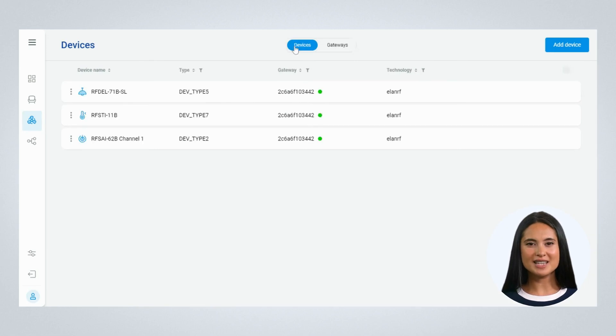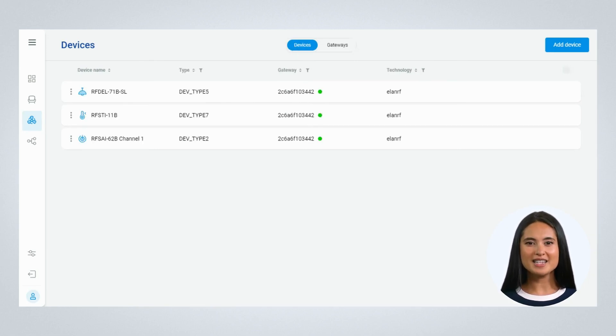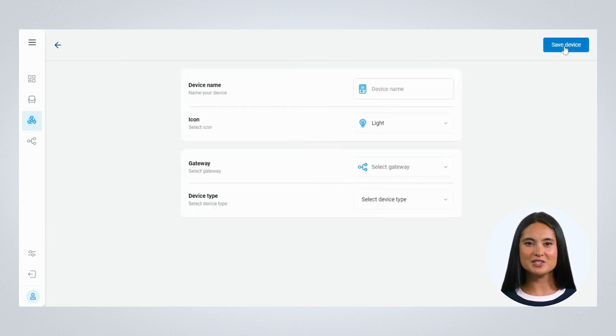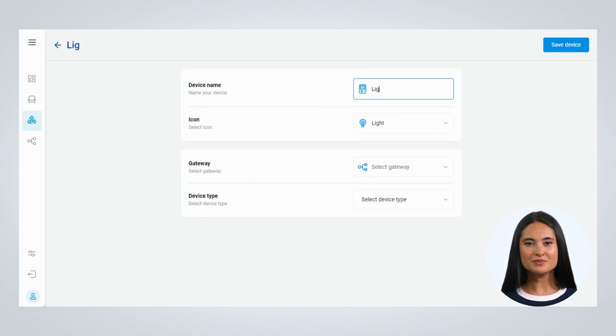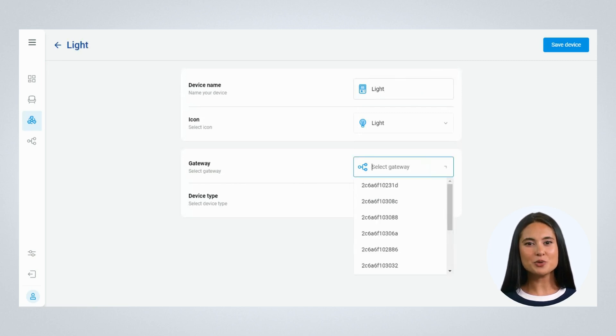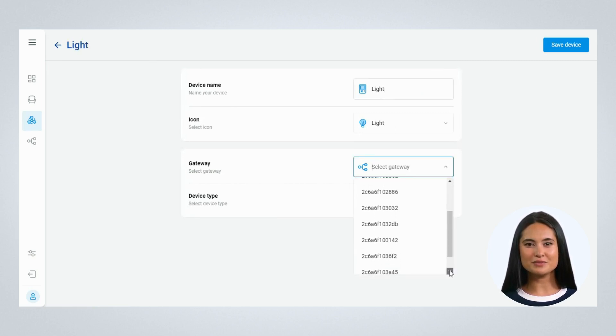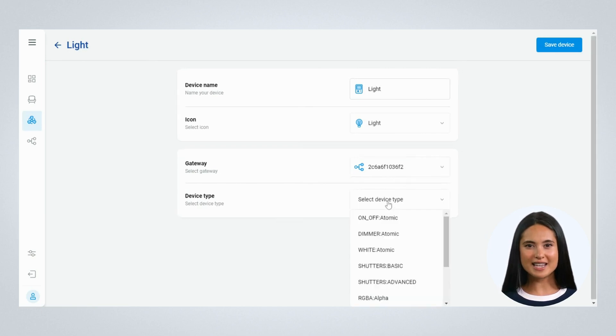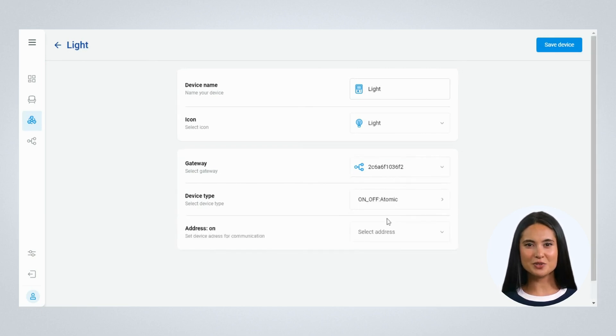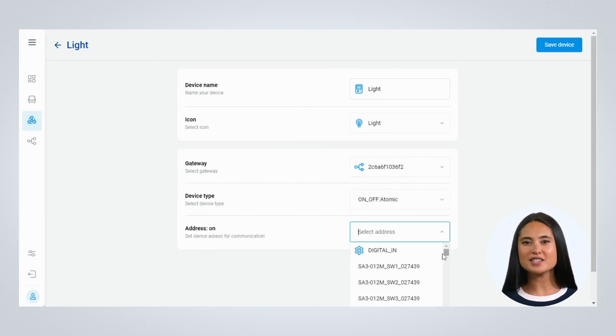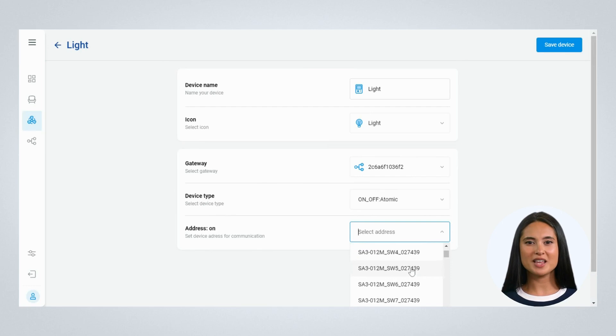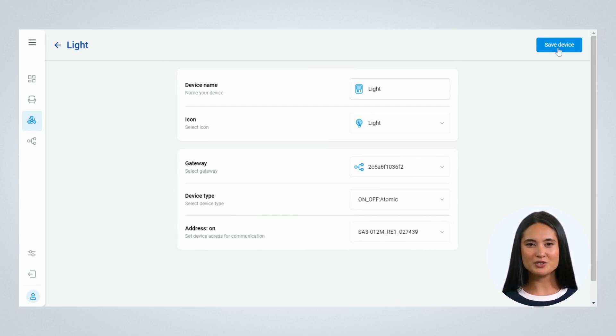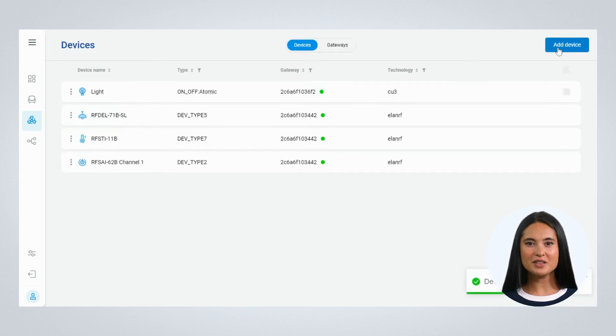The rooms and devices added through the iNELS mobile application in the wireless gateway will be added automatically. You have to manually add the bus units. Enter the device name and icon, choose the gateway using the MAC ID which the device is connected. Select the device type. All the unit addresses exported through the IDM software will appear here. Select the required address and save the device. It will then appear in the device list.